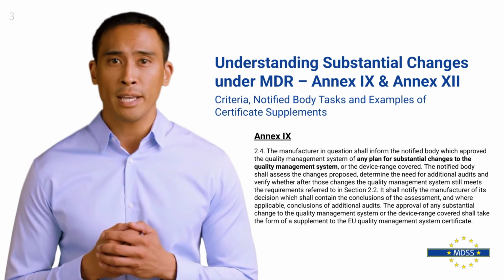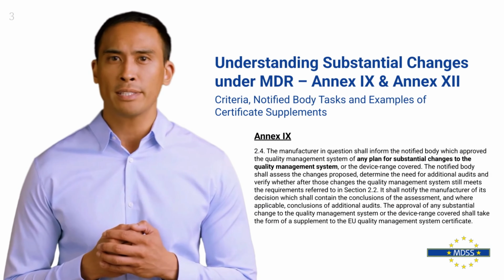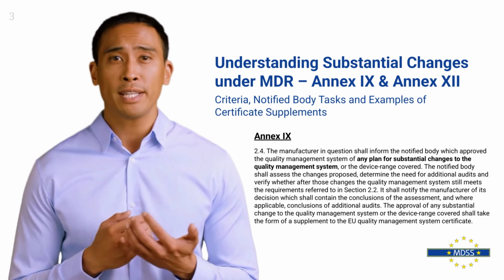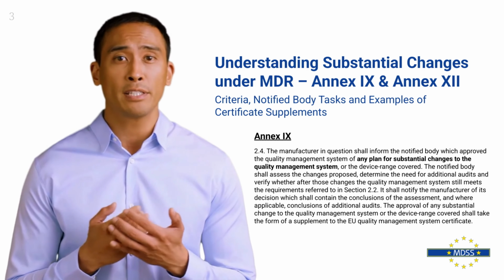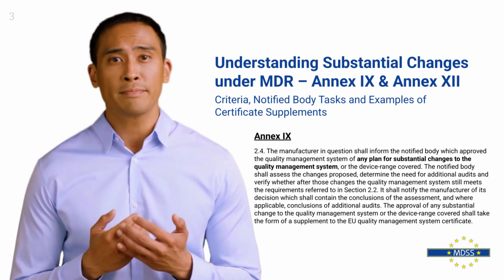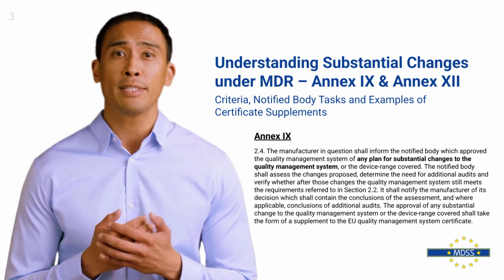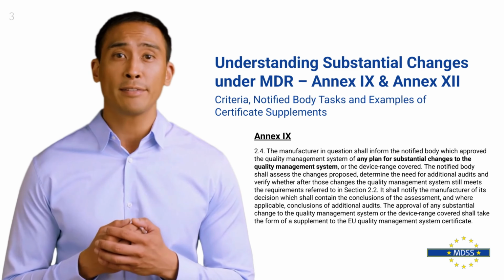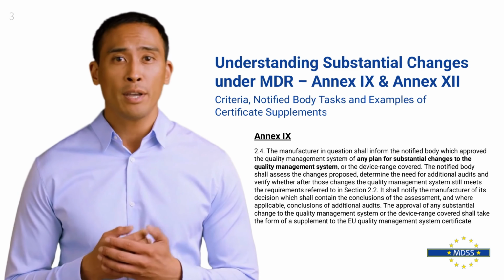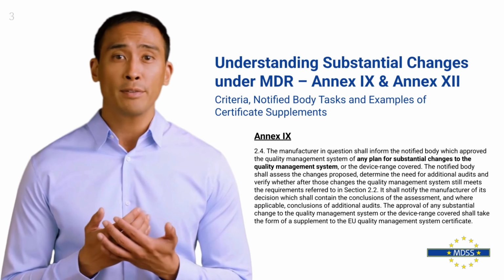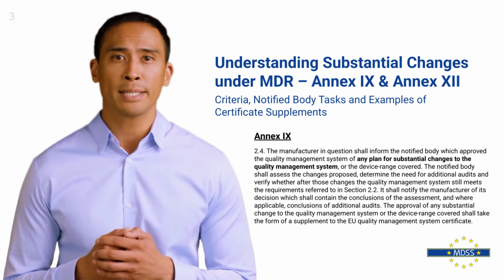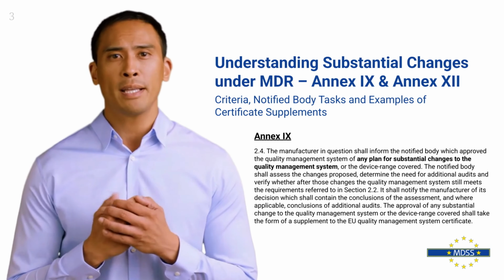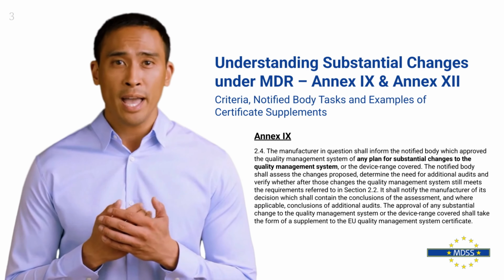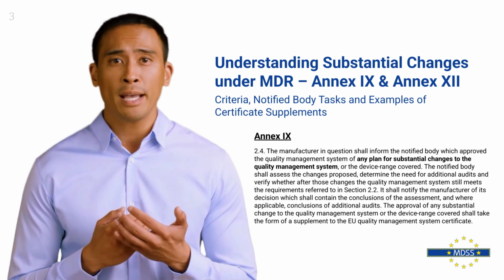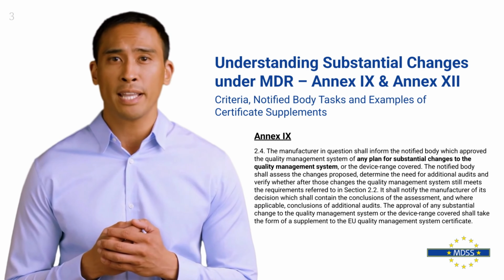Let's dive right into the topic: understanding substantial changes under the MDR. The term substantial change appears in Annex 9, Section 2.4 of the MDR. According to this section, the manufacturer is obligated to inform the notified body of any plan for substantial changes to the quality management system or the product range covered. This requirement plays a critical role in maintaining the validity of the conformity assessment and ensuring ongoing oversight by the notified body. In this presentation, we will only address the substantial changes to the quality management system.